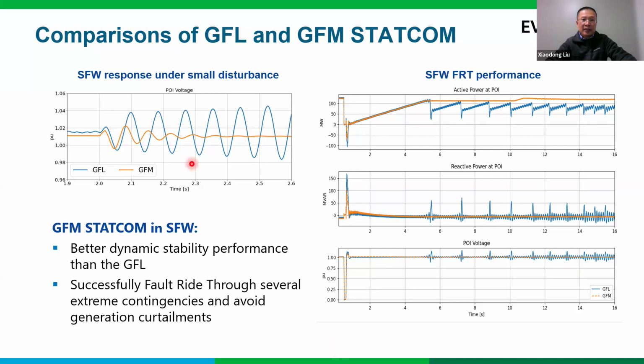All right, just as a test, we replaced the grid following STATCOM with the enhanced STATCOM and tried to observe its response, and it showed even better dynamic stability performance. Let me show you here, right? The red line, right, in the first diagram. So the oscillation mode of the grid forming STATCOM and the grid following STATCOM is almost completely suppressed in the enhanced STATCOM. So you can clearly see from here. Just a test. All right.